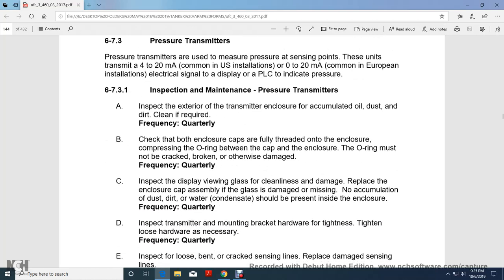Pressure transmitter. A pressure transmitter is used to measure pressure at the sensing point, with a 4 to 20 milliamp electrical signal displayed on a PLC to indicate the pressure. Inspection of the pressure transmitter. Inspect the exterior of the transmitter. Ensure there is no accumulated oil, dust or dirt, and clean if required. Quarterly, check that both enclosure caps are fully threaded, compressing the O-ring between the cap and the enclosure.